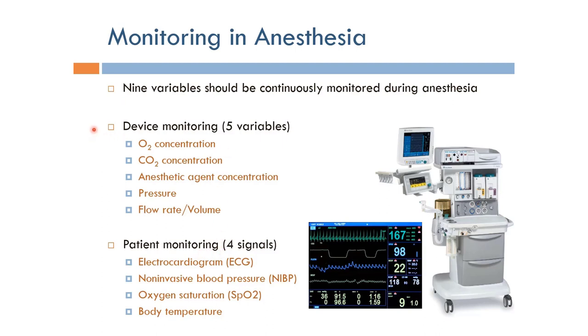If you look at the device monitoring, we have to monitor all the parameters that can cause any harm to the patient, like oxygen concentration, carbon dioxide concentration, and anesthetic agent concentration.